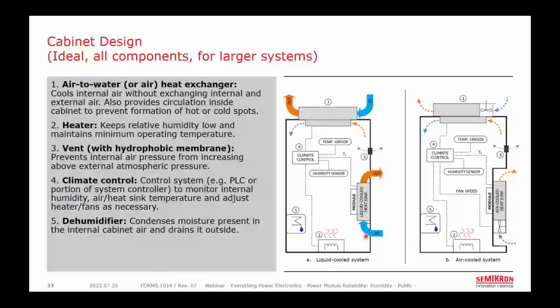And while these cabinets are sealed, they're not hermetically sealed. And we have vents here with a hydrophobic membrane that are used to ensure pressure equalization. And these membranes repel liquid water and dirt, but they allow air to flow through. So they don't necessarily block water vapor.